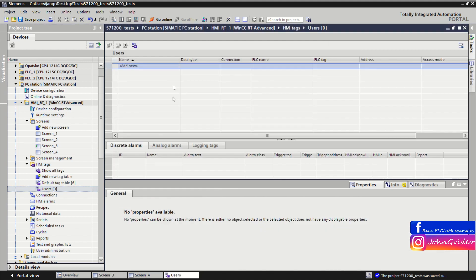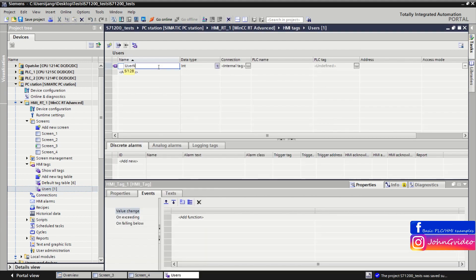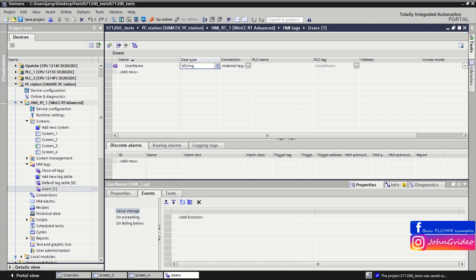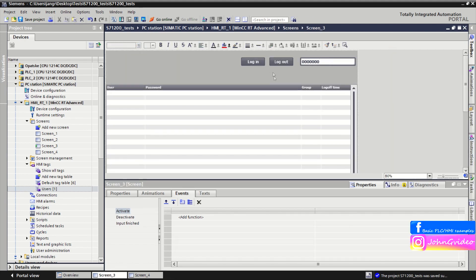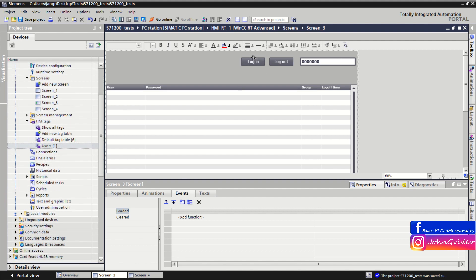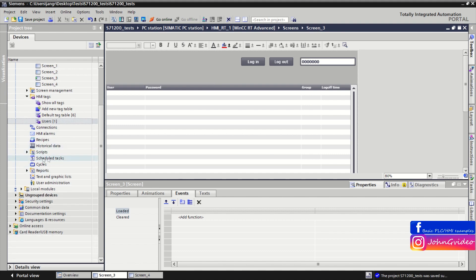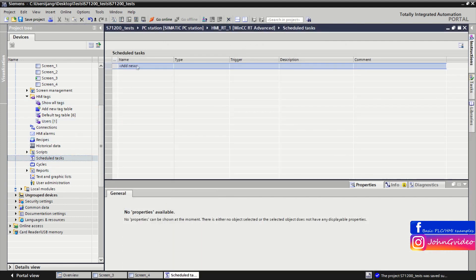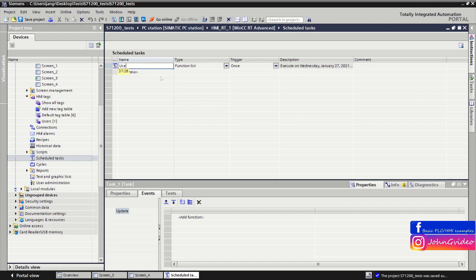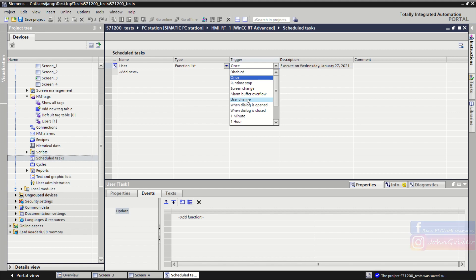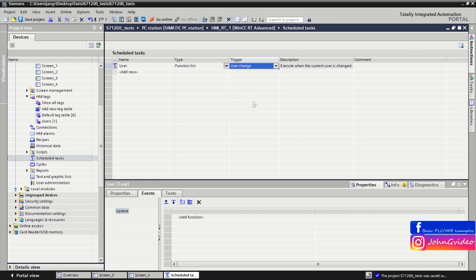For this, we create a tag called 'username' of data type string — this will be an internal tag. We also create a new task called 'user', and the trigger of this task will be 'user change' — so whenever a user changes in your HMI runtime, this task will trigger on user change.